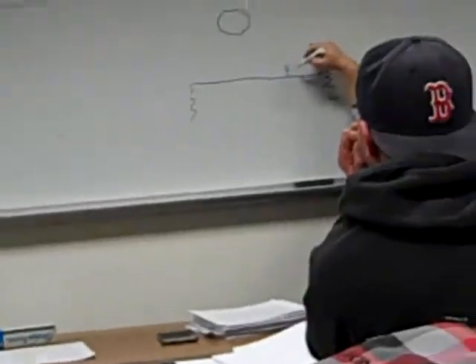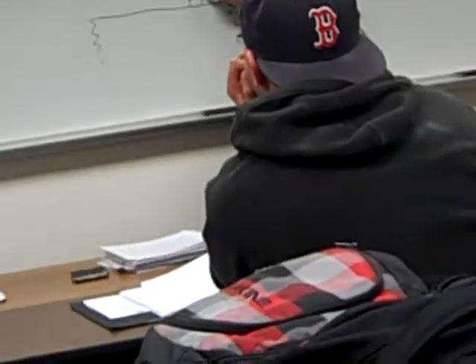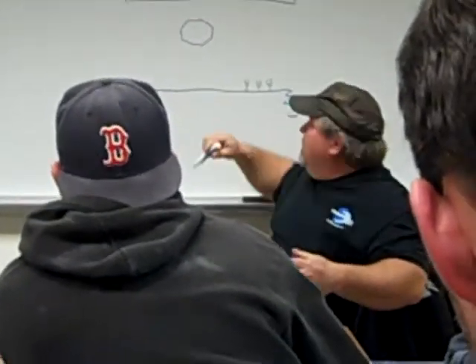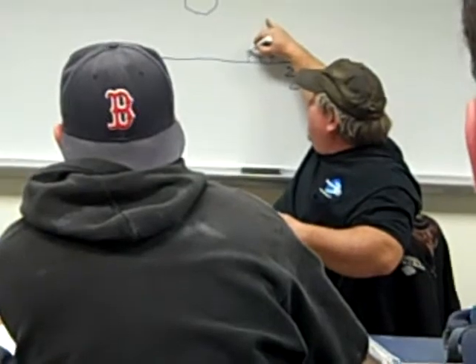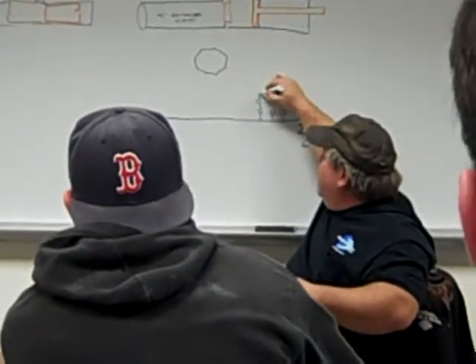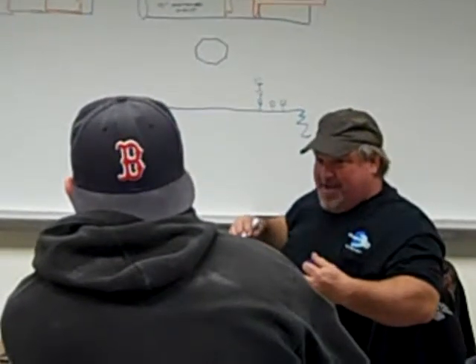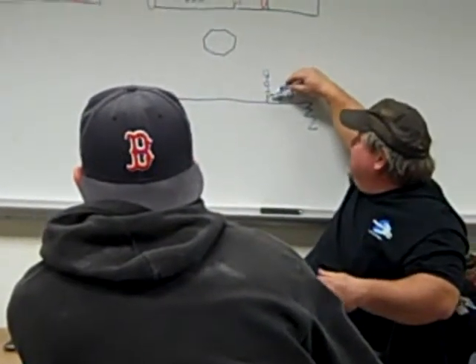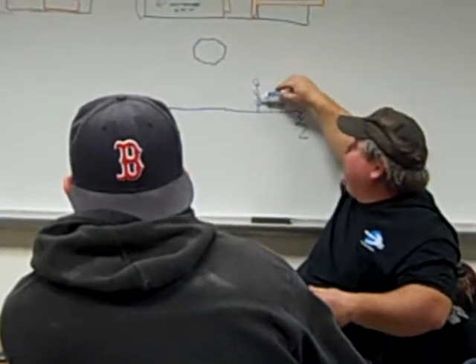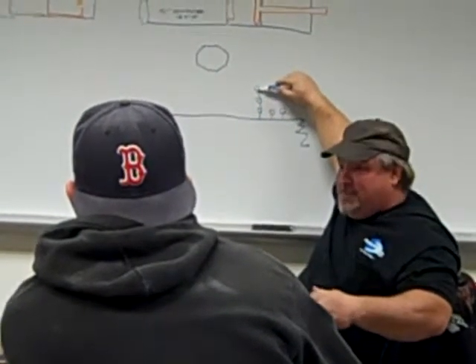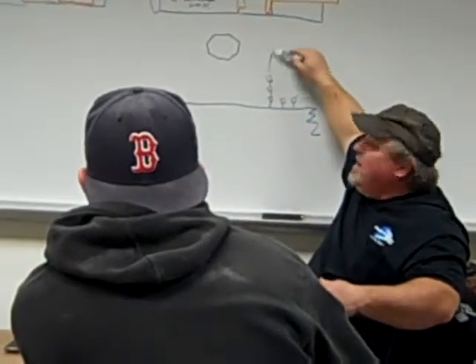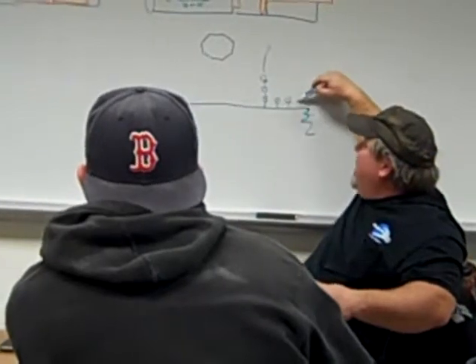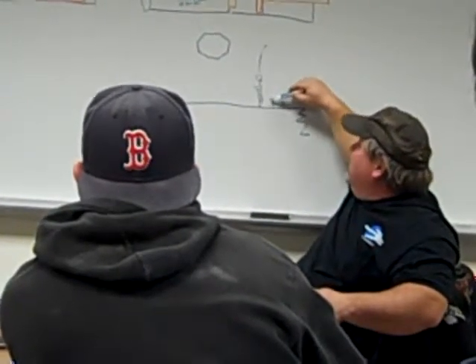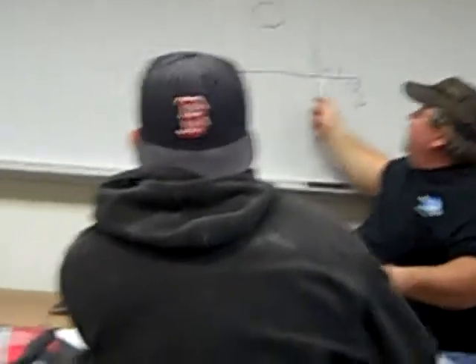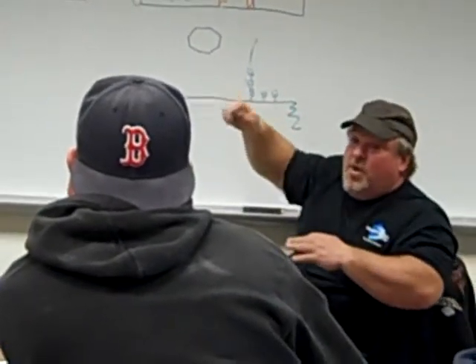You can have multiple pressure relief valves if you want. So if one fails, you've got a backup, and you've got a backup for that one. But you can't put this relief valve that way and then come up here and put another one here and another one here. That doesn't work. That's in series. This would have to fail, and then this one would have to fail, then this one would have to fail. So you'd have to have all three of them fail before it would vent out the top. You can put them one right after another. This one could fail and it would vent, and these two could be fine. So you can install them that way, but never install them one on top of another.